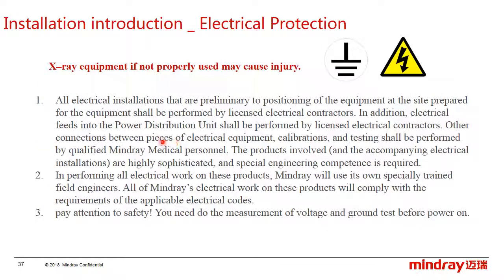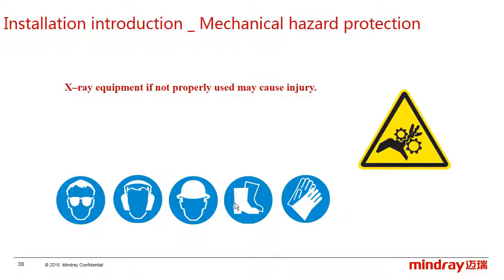Besides, X-ray equipment, if not properly used, may cause injury. First, all the installation, calibration, and testing should be performed by qualified medical personnel. Second, in performing all electrical work on these products, Mindray will use its own specially trained field engineers. Third, the engineer should measure the voltage and run tests before power on during the mechanical installation. Improper use may cause serious damage, so labor protection tools are necessary, such as goggles, ear plugs, and a safety helmet.